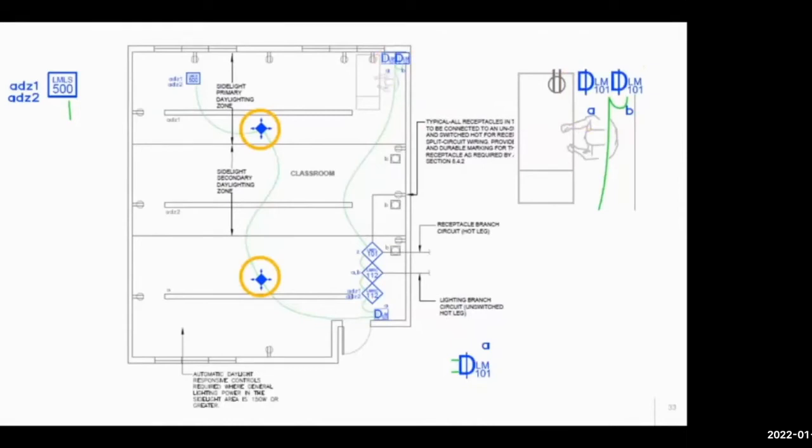All of these devices, the switches, the sensors, both daylight and occupancy detection, are feeding that information to the central controllers that are operating the power and the dimming control inside that space. Additionally, there's another controller here that's also handling, in conjunction with the lighting controls, the automatic receptacle control. It's using the occupancy sensors to shut off the receptacles when the space is unoccupied, which is a provision inside the ASHRAE 90.1 code.